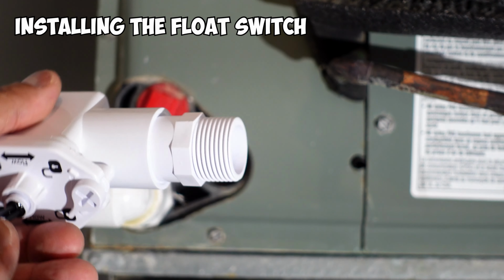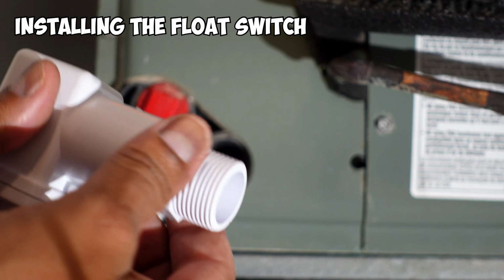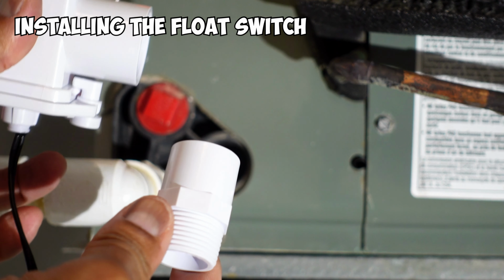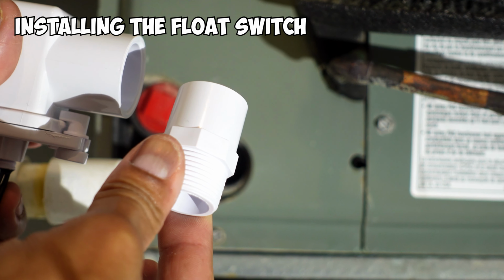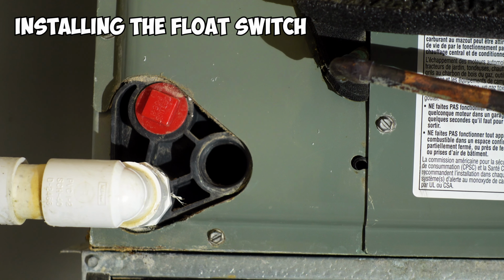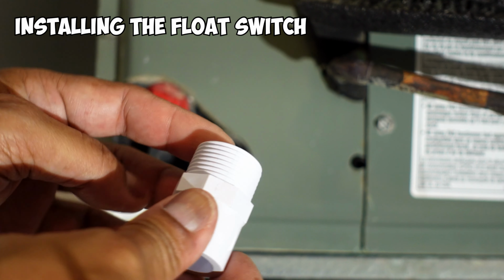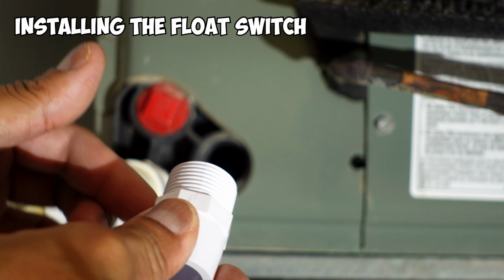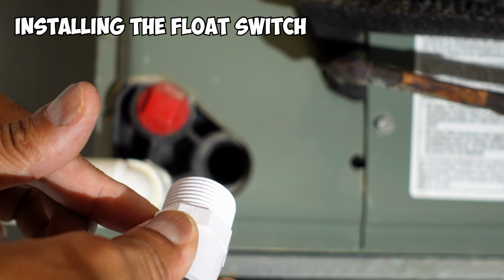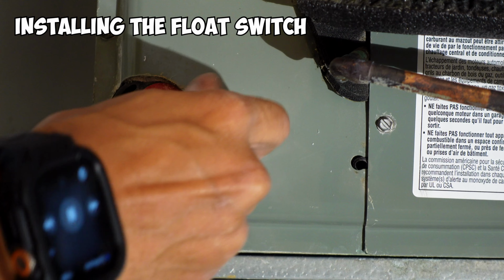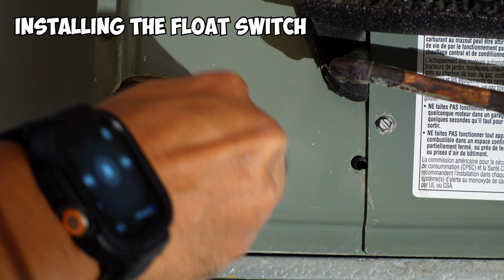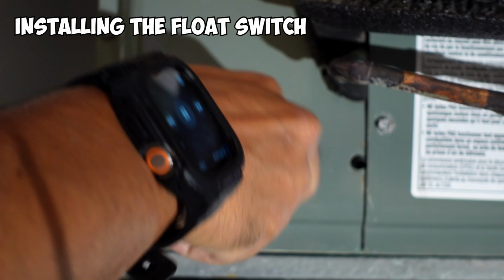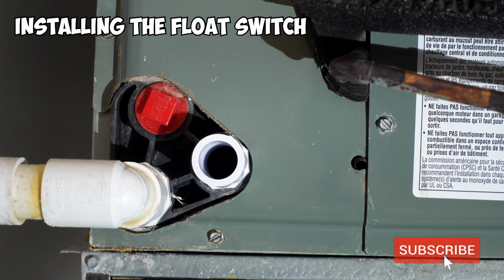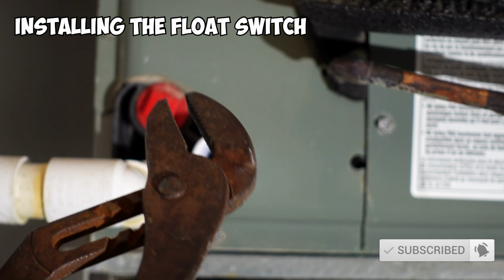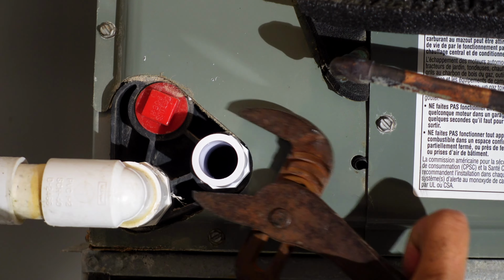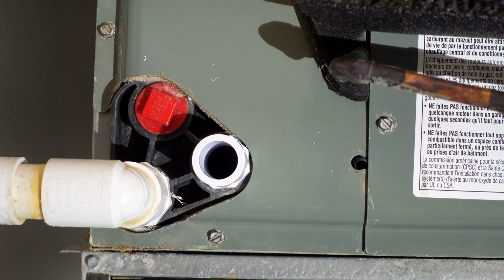Once you've done that, you can now take your float switch and separate it into two pieces. One piece is going to be the actual float switch and the other piece is going to be a PVC adapter. Take the PVC adapter, and if you have some Teflon, put the Teflon on, and then screw it into your AC unit in the drain plug hole. Once you've done that, next you take a pair of channel locks or pliers and tighten up the PVC adapter until it's nice and snug. Once it's nice and snug, you're ready to move on to the next step.